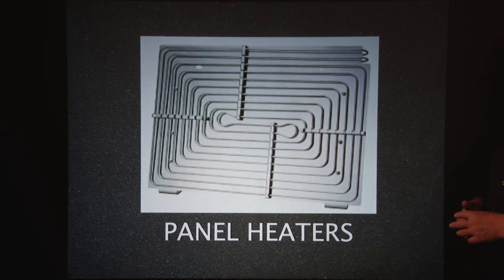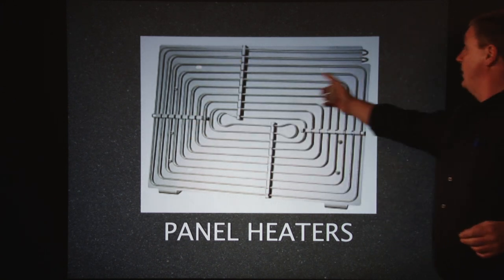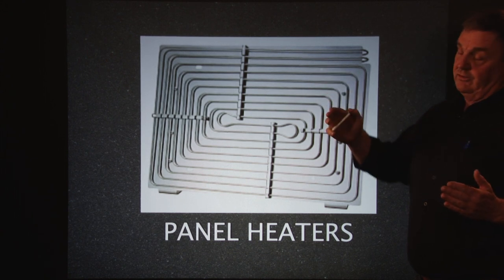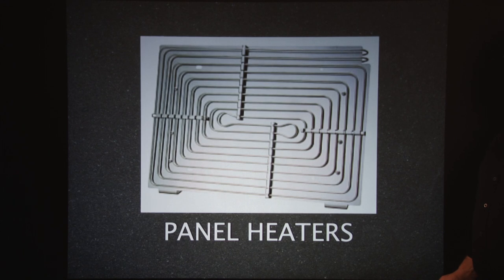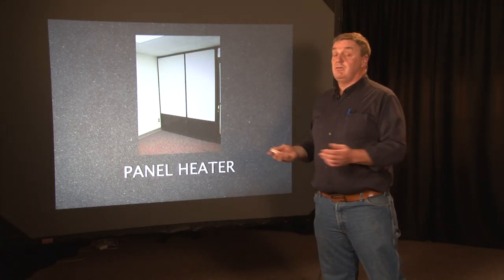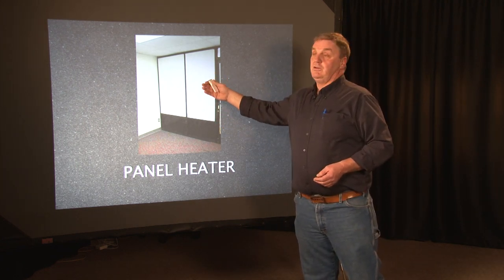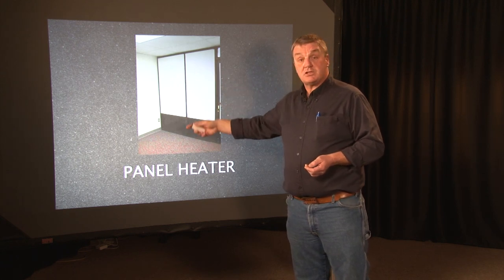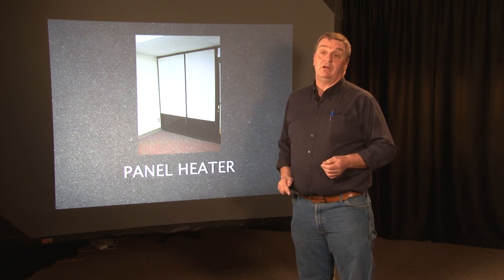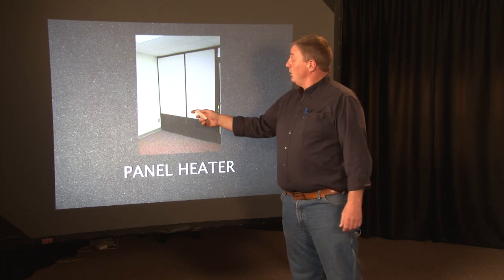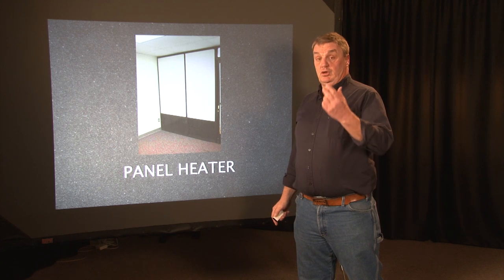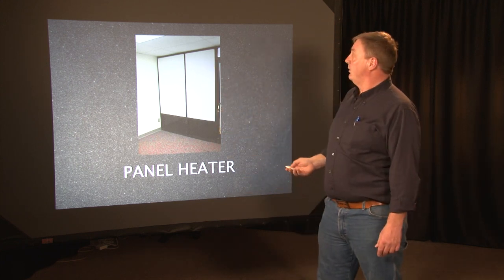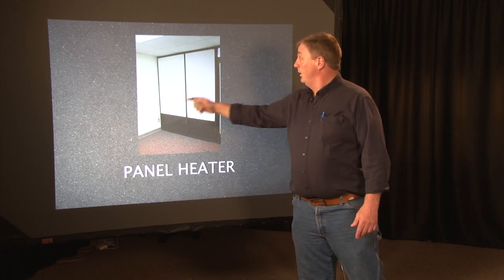This is a panel heater without the rest of the panel on — it explains what happens inside. You have a high resistance wire with an electrical current through it that gets hot because of the resistance. The heat is transferred to the panel depending on how it's mounted on the wall. With panel heaters, basically all you can do is check: do they have an electrical supply? Do they feel warm when you touch them? Are they scratched or damaged? You may not need your third-party man to tell you that's working. You will just need to make sure there's a supply there, know where the breaker is to turn them off in case they overheat, and there'll be a thermostat control somewhere.